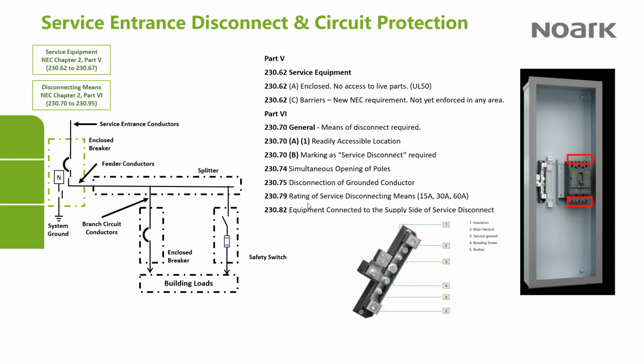And then equipment connected to the supply side of the service disconnect. So I'm not going to go into the details. There's about 6 or maybe 8 exceptions. The general rule of thumb is that nothing can be connected to the utility side of a service disconnect. Now, the exceptions are for things like metering equipment, surge protection devices. There's a bunch of exceptions. But there's nothing there that I would call a consumer of any significant amount of power that's allowed to be connected to the line side of the breaker.